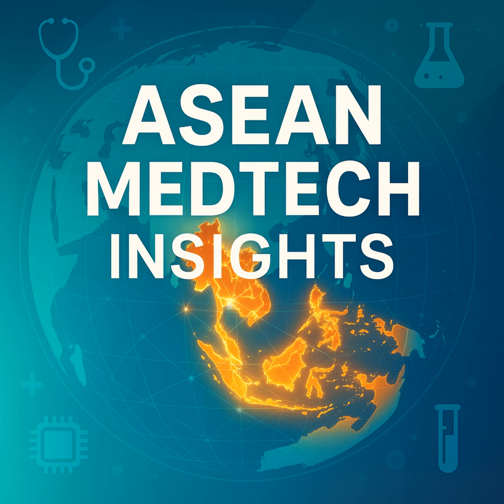The very first and most critical step for any foreign manufacturer is to appoint a Malaysian Authorized Representative, or AR. This is not just a formality. Your AR is legally responsible for your device in the country, manages the registration submission, and acts as the primary contact for the MDA. You cannot register a device in Malaysia without one.